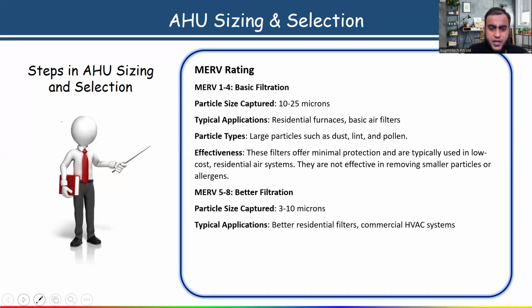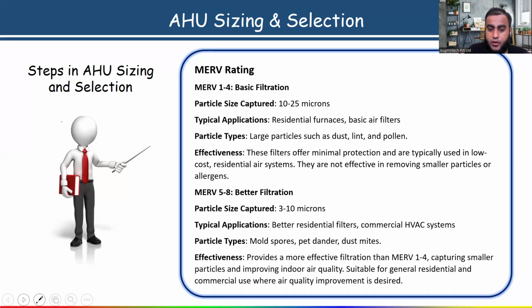Also, we are using this MERV 5 to 8 rating filter. The particle types which they capture are mold, spores, pet dander, and dust mites. It provides more effective filtration than the MERV 1 to 4 rating filter which I have shown you, capturing smaller particles and improving indoor air quality. So that is why it is suitable for general residential and commercial HVAC systems where air quality improvement is desired. In that application, you can use this MERV 5 to 8 rating filter.